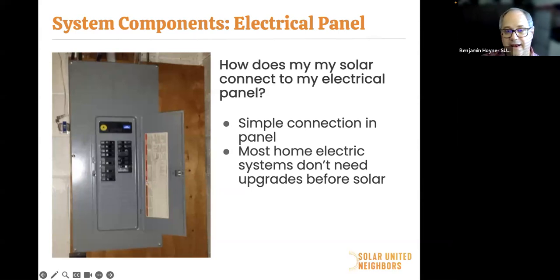Also important to note, one of the first things the solar installer will do is ask you for a photo of your electrical panel that looks just like this. That's because they want to see if you have any breaker availability. You'll need a 2-pole 240 breaker to run the solar into your electrical panel. Most homes don't need system upgrades, but your installer will be able to tell that pretty quickly. If you did need an electrical panel upgrade because your panel is full or too dated, they can certainly do that - that's part of the co-op.